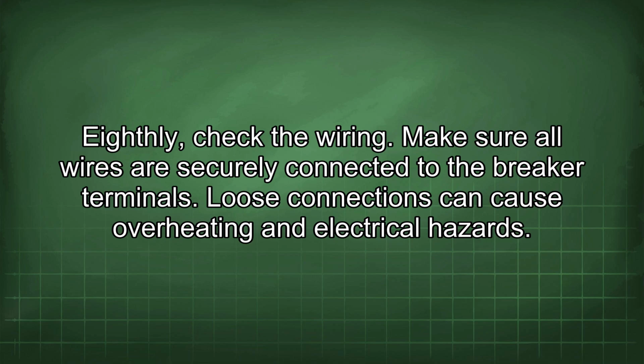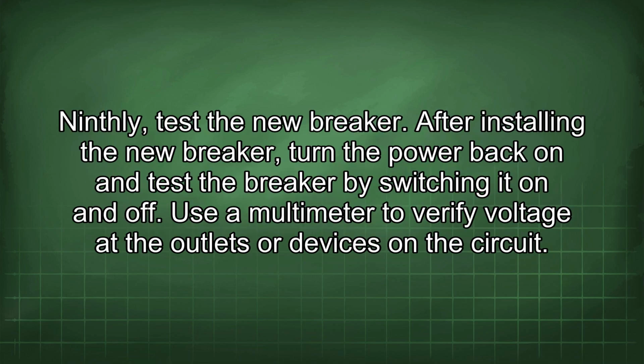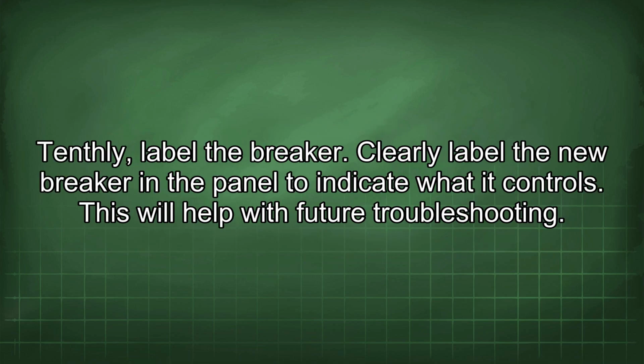Eighthly, check the wiring. Make sure all wires are securely connected to the breaker terminals. Loose connections can cause overheating and electrical hazards. Ninthly, test the new breaker. After installing the new breaker, turn the power back on and test the breaker by switching it on and off. Use a multimeter to verify voltage at the outlets or devices on the circuit. Tenthly, label the breaker. Clearly label the new breaker in the panel to indicate what it controls. This will help with future troubleshooting.